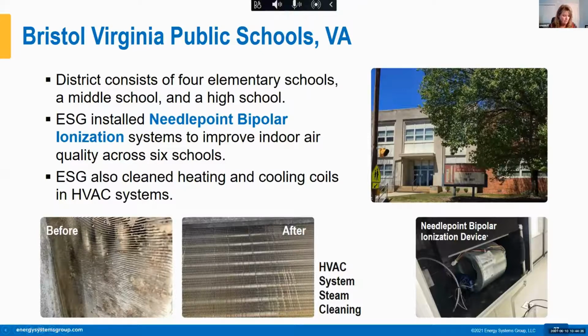The second one is our friends in Bristol, Virginia Public Schools, an indoor air quality project only, completely funded by ESSER funds, done at the end of 2020. We installed the needlepoint bipolar ionization systems into the existing HVAC systems. As part of that, we did extensive deep cleaning and steam cleaning of the HVAC systems, the cooling coils and heating coils. You want to start with a clean slate. We did thorough cleaning, the bipolar ionization installation, and completed a study with recommendations on filters going forward, identifying which systems could continue using MERV 8s and which needed upgrading to MERV 13s.